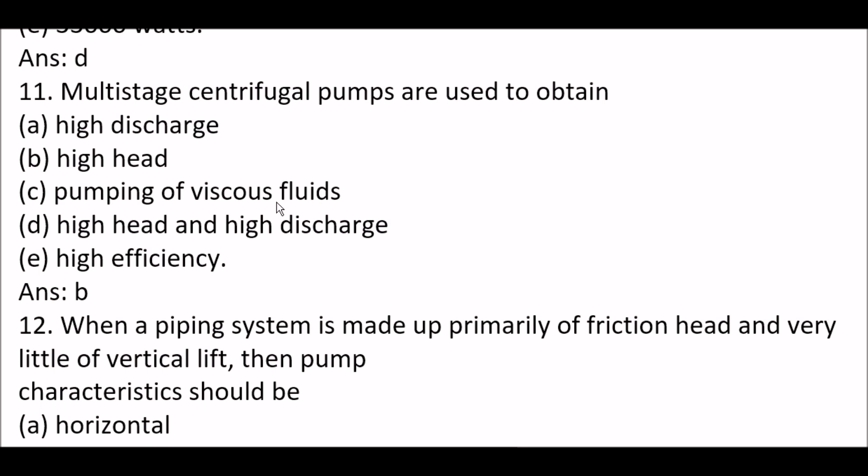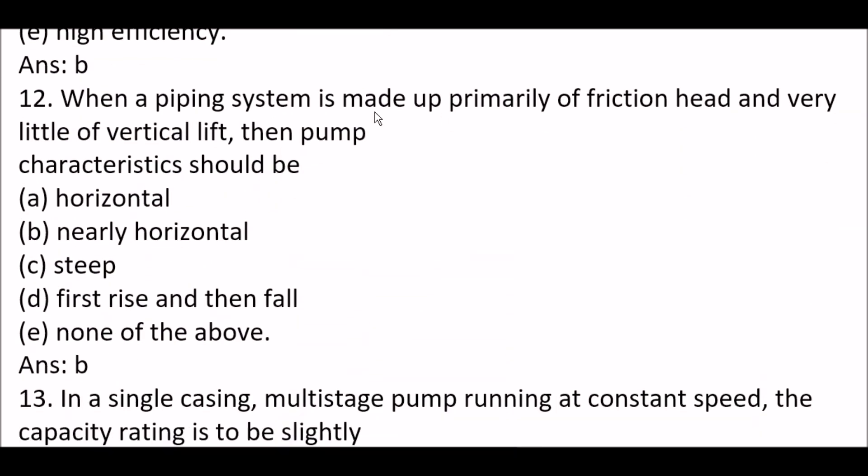Next question. Multi-stage centrifugal pumps are used to obtain high head. Next question. When a piping system is made up primarily of friction head and very little of vertical lift, then pump characteristics should be nearly horizontal.